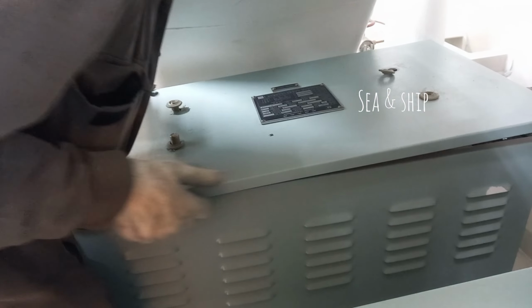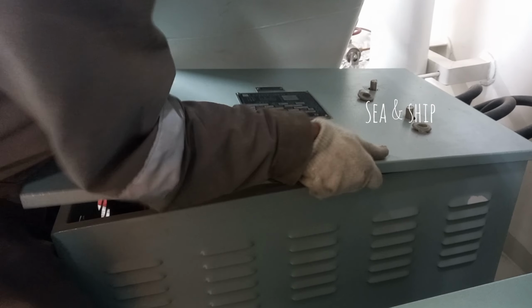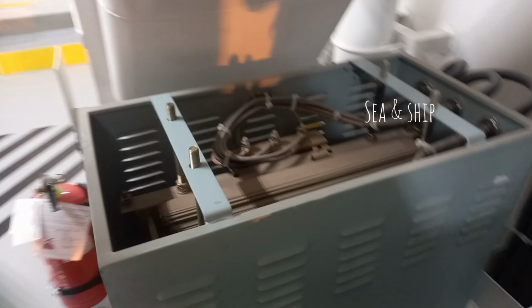So first, always isolate the transformer by switching off the supply from the main switchboard, opening and locking the circuit breaker, and placing a proper 'men at work' warning with lockout-tagout procedure. Then never assume power is off; always verify zero voltage using a multimeter or voltage tester on both input and output terminals before touching anything.